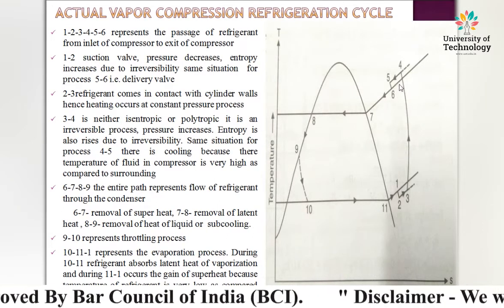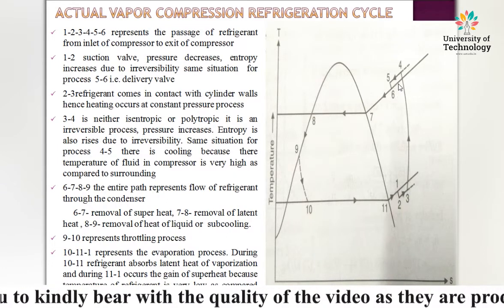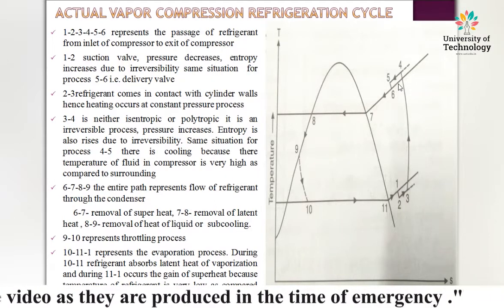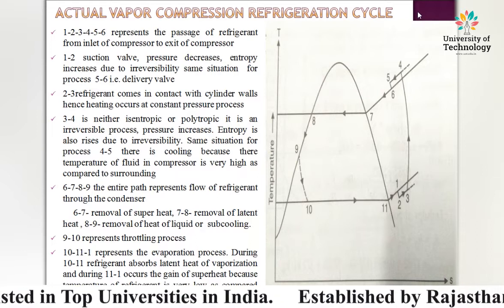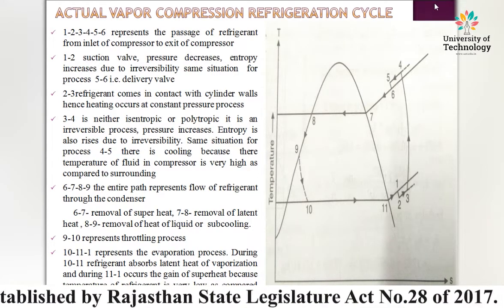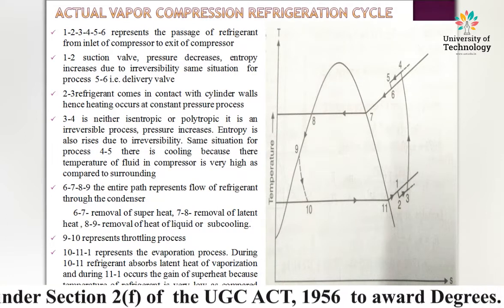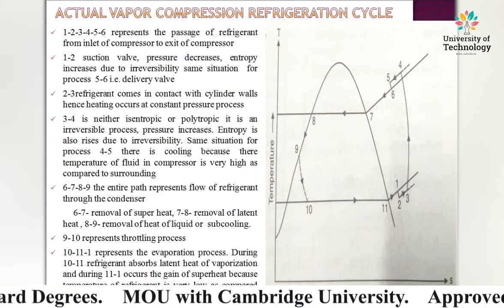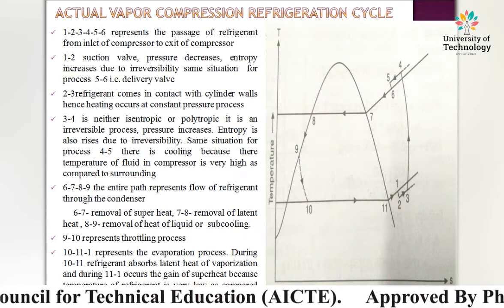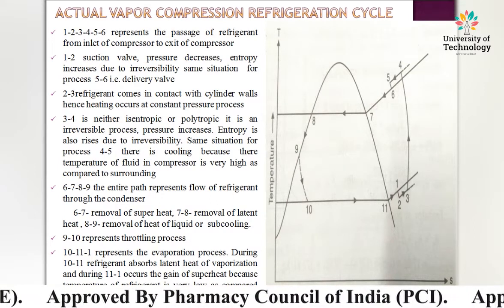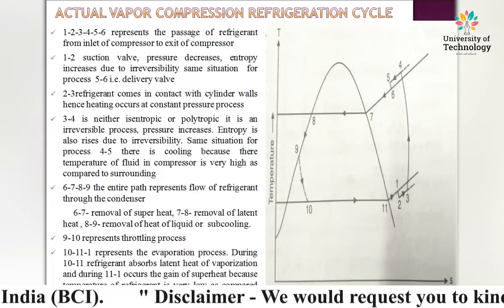After compression, from 4→5, the temperature and pressure of the refrigerant are very high relative to the surroundings, so cooling of the refrigerant takes place at constant pressure. Then, from 5→6, the delivery valve causes a throttling process in which pressure drops and entropy rises due to irreversibility. This completes the 1-2-3-4-5-6 passage through the compressor.